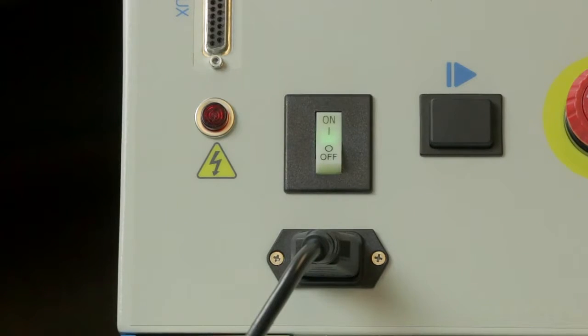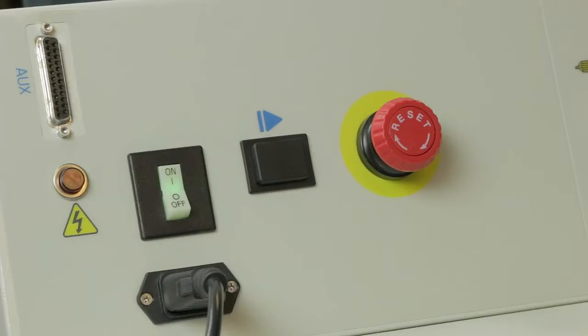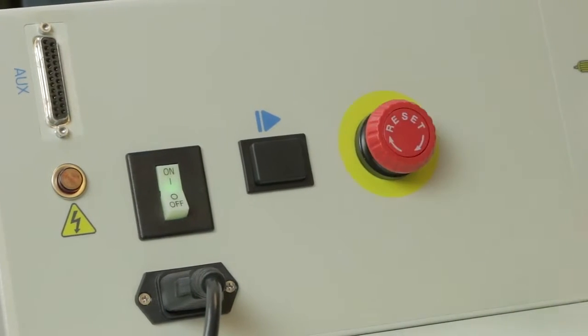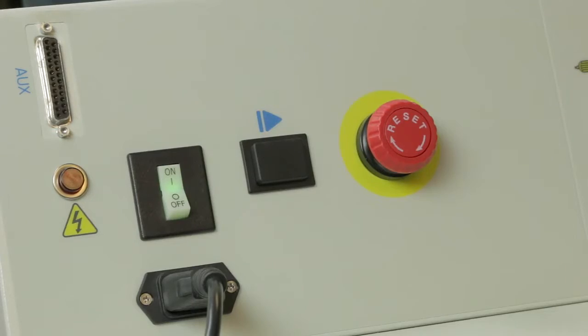As a safety feature, anytime the test leads are connected to the high voltage power supply, the warning lamps on the power pack will light up, and the words "Leads energized" will appear on the DX's screen. If for any reason you need to quickly disconnect power to the test leads, press the equipment stop button. This can be reset by turning it.